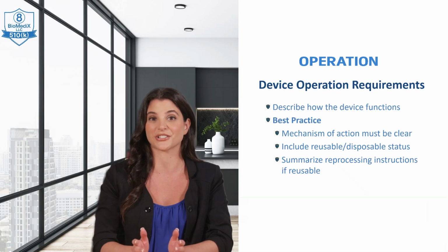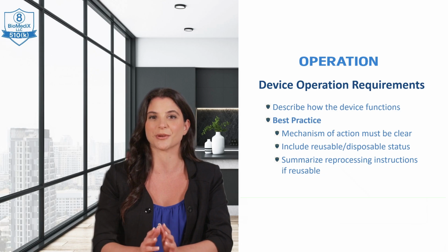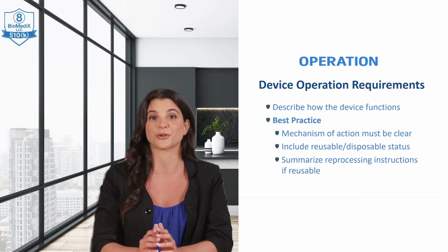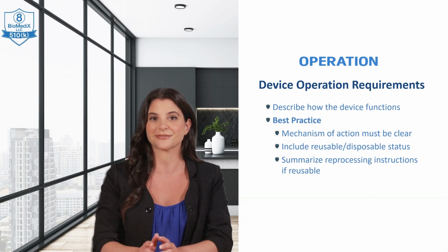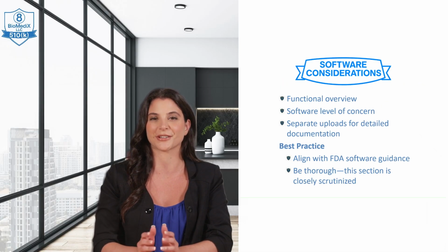Regarding principles of operation, you're required to explain how the device achieves its intended purpose. Detail the underlying scientific principles: mechanical, electrical, chemical, optical, thermal, and so on. Also, state whether the device is reusable, disposable, or implantable. The best practice here is to describe the mechanism of action clearly. For reusable devices, include a summary of reprocessing instructions. This ensures FDA understands how your device performs and how those performance claims are supported.